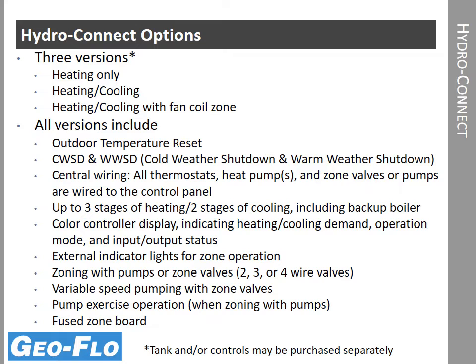Central wiring is a feature that all 3 options include. So the thermostats, heat pump, and zone valves or pumps are all wired to a central location. Up to 3 stages of heating and 2 stages of cooling is available. And that includes a backup boiler, so that we can choose a system that might have less loop requirements and maybe a smaller heat pump as a result.